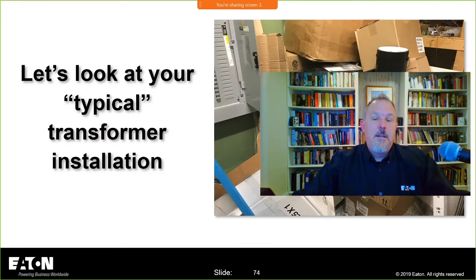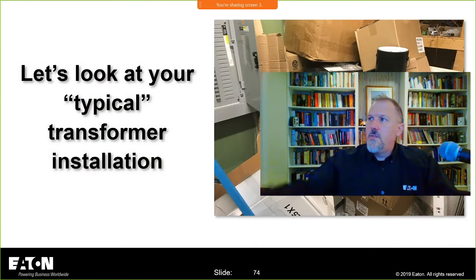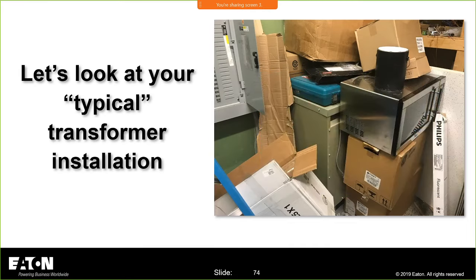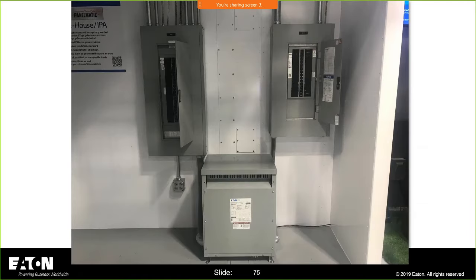And personally, I like my example of your typical transformer installation, right? So your typical transformer installation is something like that you would see in a power distribution system. For those of you on YouTube, that's sort of what I'm talking about there. So that's unfortunately a typical transformer installation, but in reality, what you would hope is that your installation is probably, hopefully, more similar to something like this. You have a downstream panel board, you have an upstream panel board feeding that transformer. To know what's the secondary and what's the primary, I usually look at the conductors. The primary is going to have a smaller conductor conduit going to it. The secondary is going to have a larger conduit coming out of it just because of the voltage transformation.